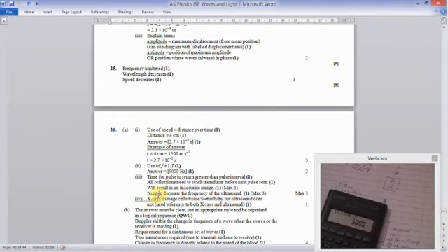There we go. Right, okay, so if the time for the pulse to return is greater than the pulse interval, all reflections need to reach the transducer before the next one. Otherwise this will produce an inaccurate image, in other words, the idea of interference. We need to decrease the frequency of the ultrasound. So that's one thing you can do. If you're decreasing the frequency, remember you're changing that time period. It's the same idea. You could talk about frequency or time period.